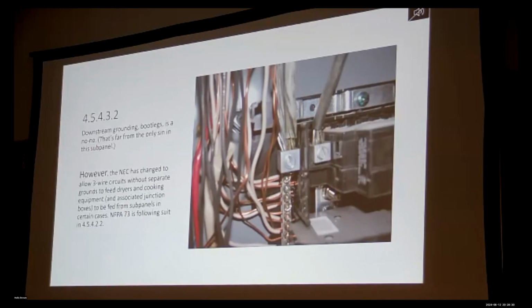And I know if you get an indication of that, you're going to cite it or say, have an electrician check it, or maybe even open and look and see, oh, they ran a wire from here to here. Oh, bleh. But now they're saying, look, under certain circumstances that are delineated, including that you isolate that neutral from the can, you're allowed to maintain that. That's a change.